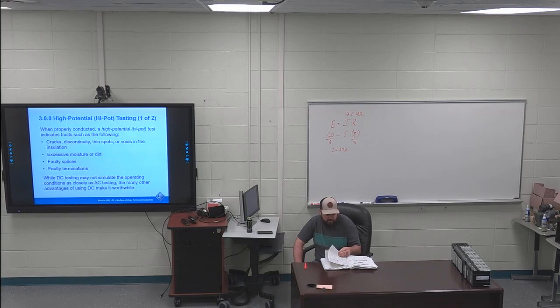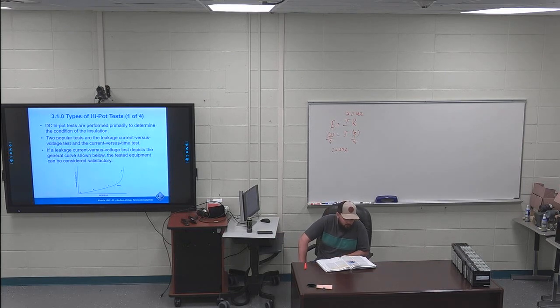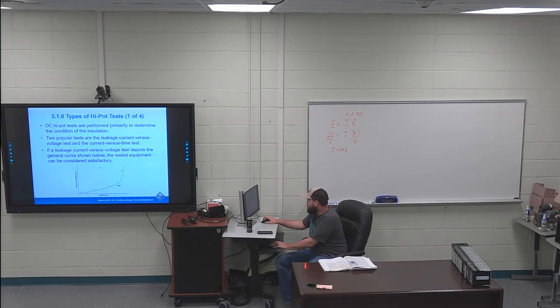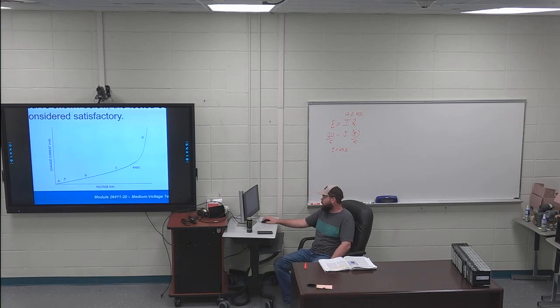Moving on to page 30. Types of high pot tests, 310. First sentence is highlighted. DC high pot tests are performed primarily to determine the condition of the insulation. So for a high pot test, you can see up here on the board, you increase voltage to see what the current does. And whenever the current starts to spike, that's where your insulation is breaking down.